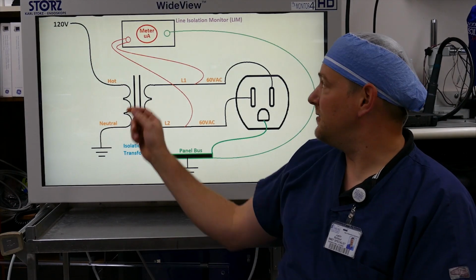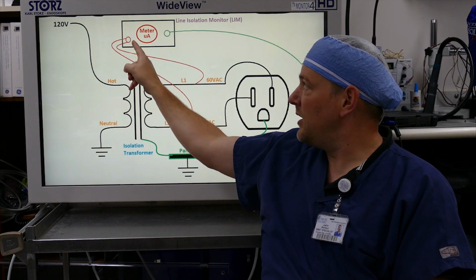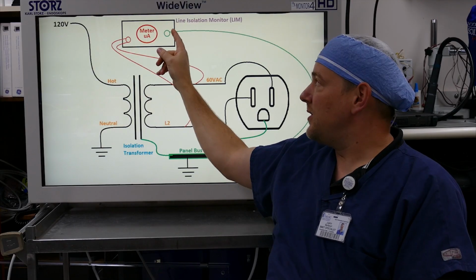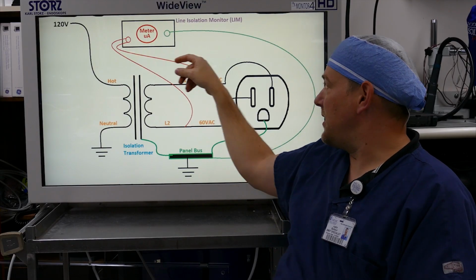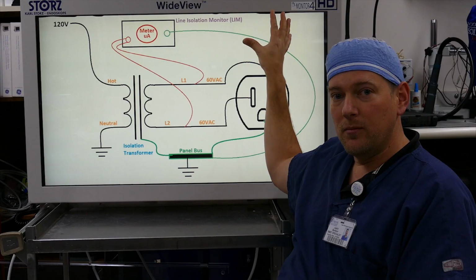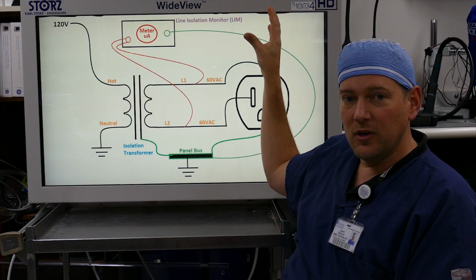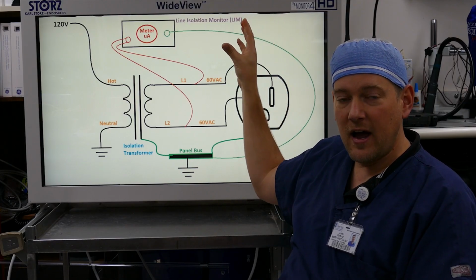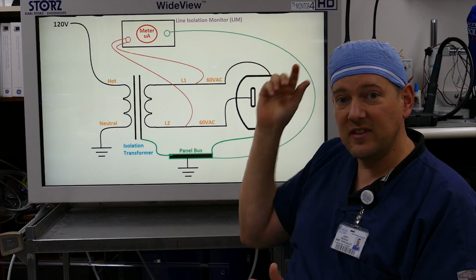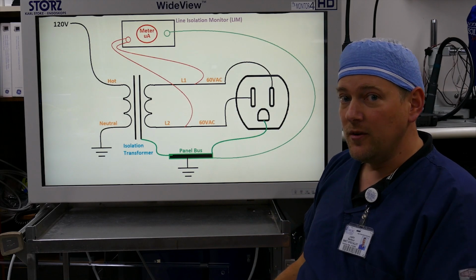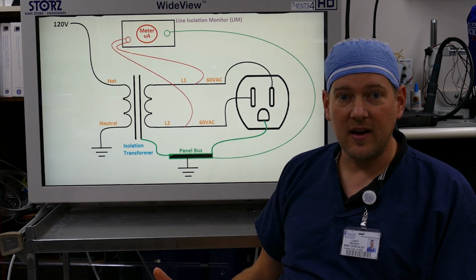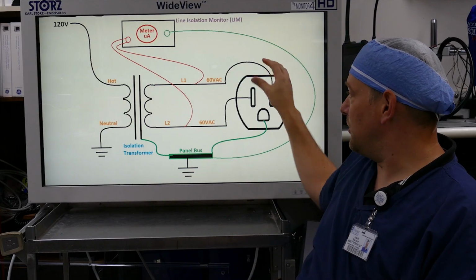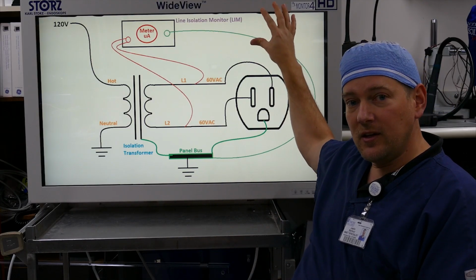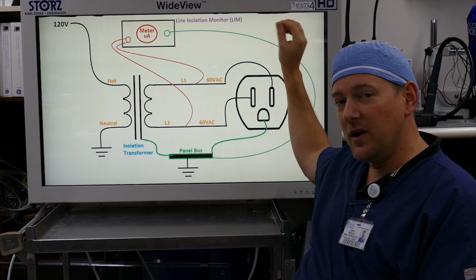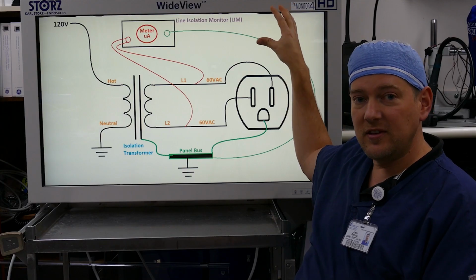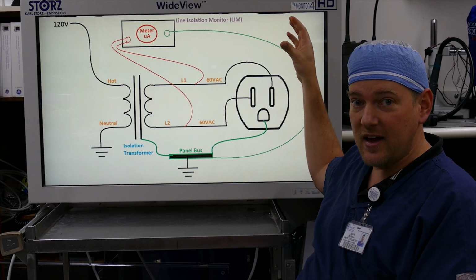If current ever exceeds 5 milliamps between ground and L1 or L2, then your meter will alarm, and it buzzes inside the operating room. Now this is pretty similar to a GFI that you find at your house, except a GFI will disconnect the circuit. And of course, there's no way you want a circuit disconnected in an operating room. So all this will do is there's going to be a buzzer on the alarm with a flashing light. It'll buzz inside the operating room, allowing the staff to see that there is a potential hazard someplace.